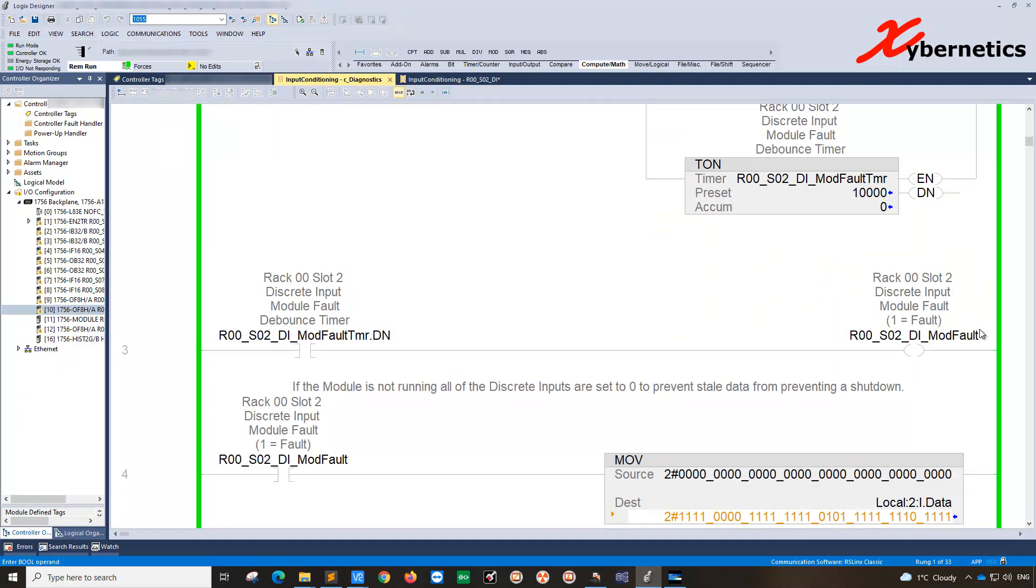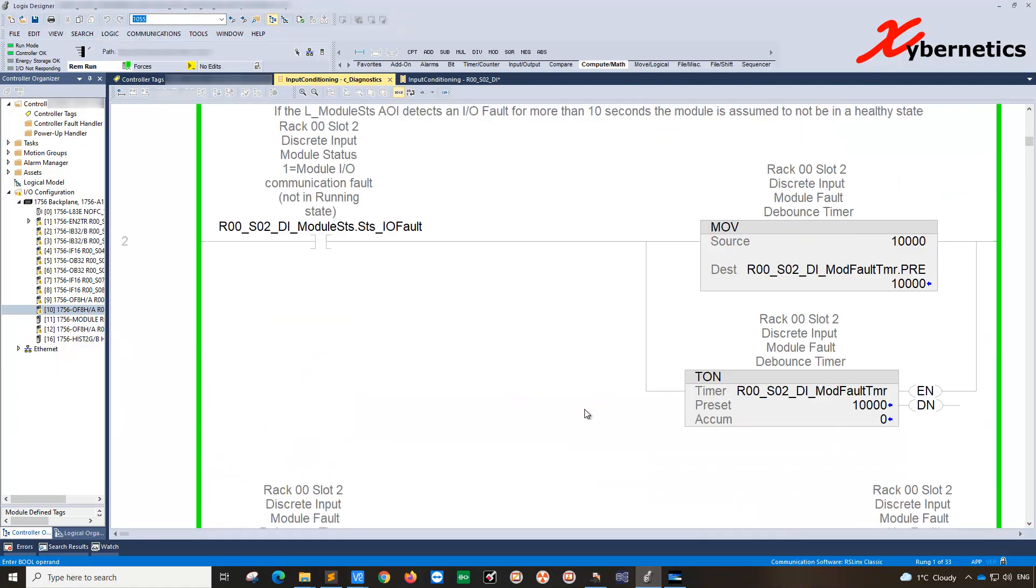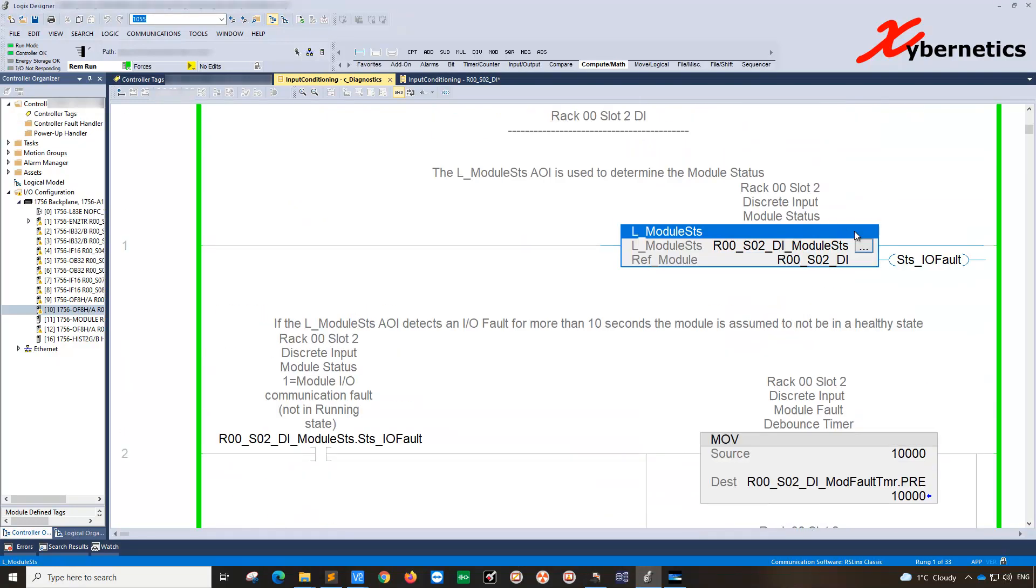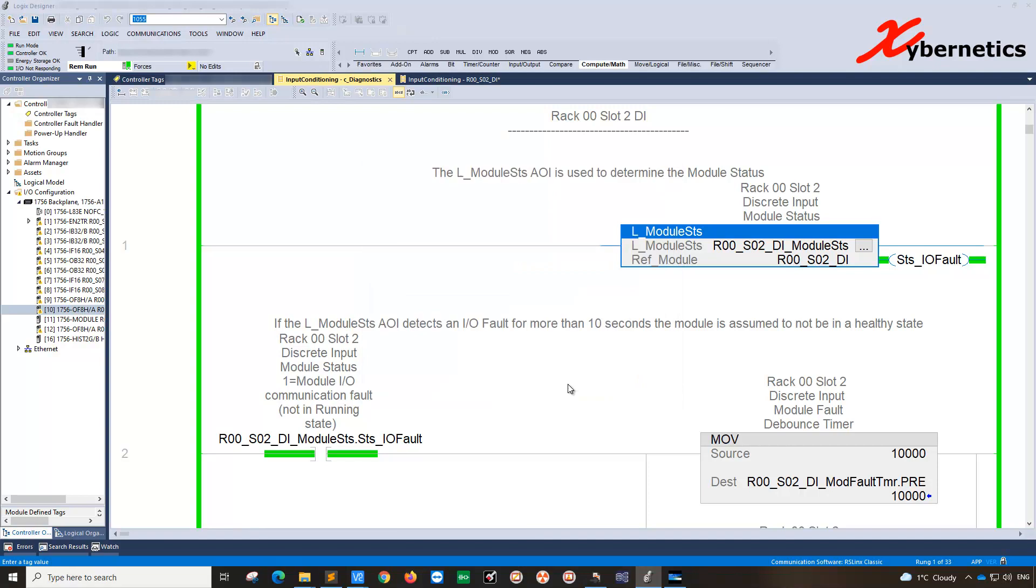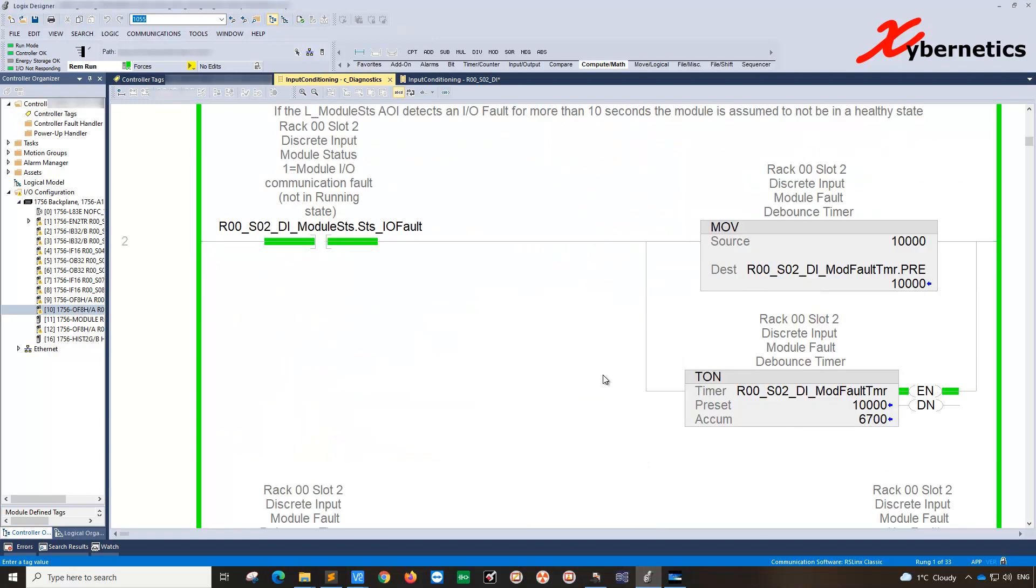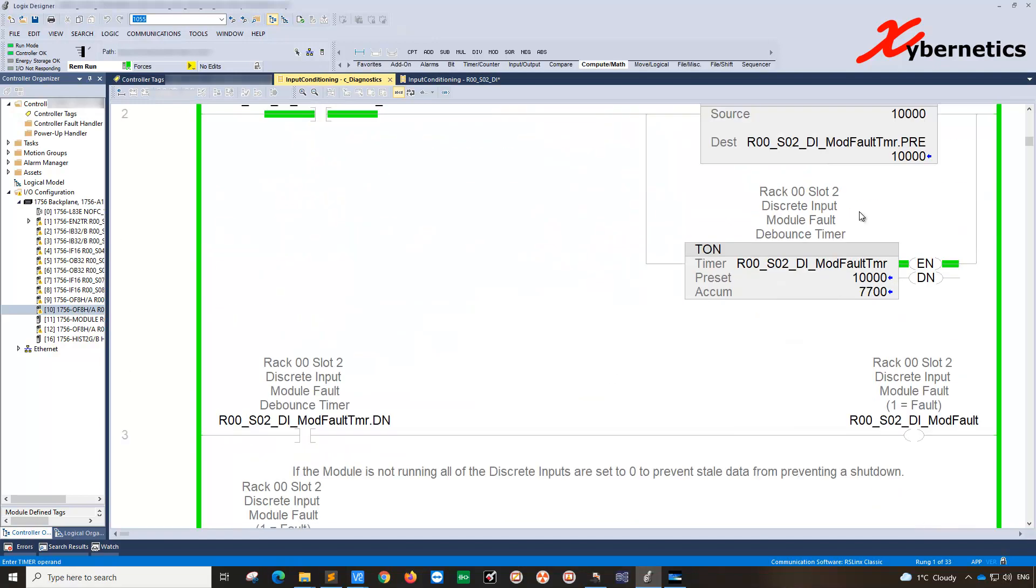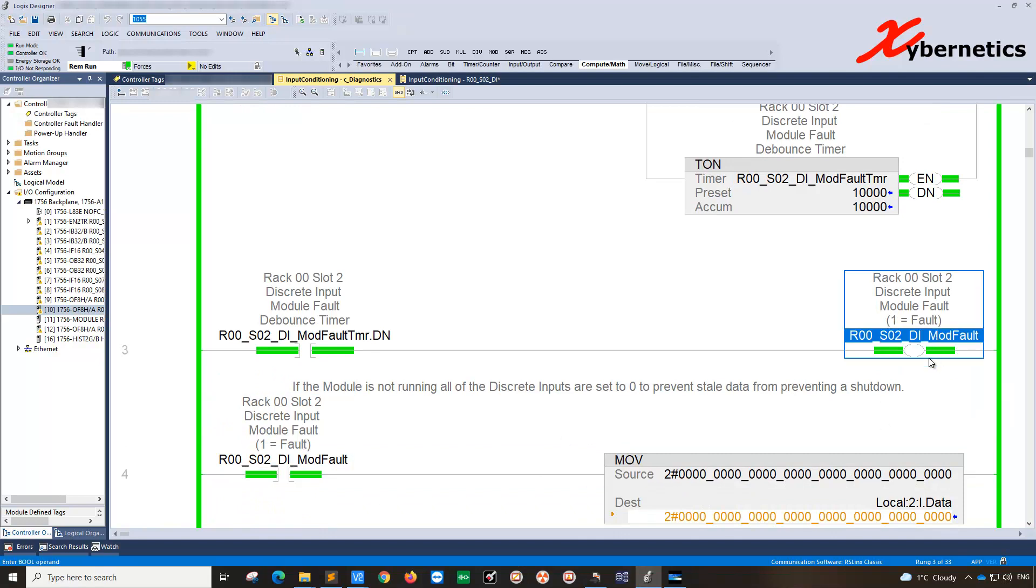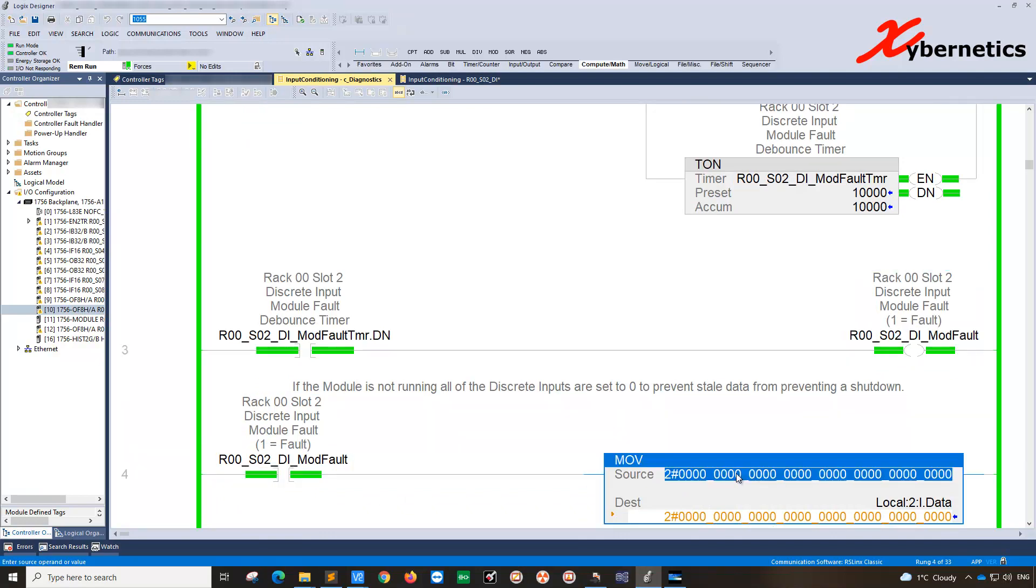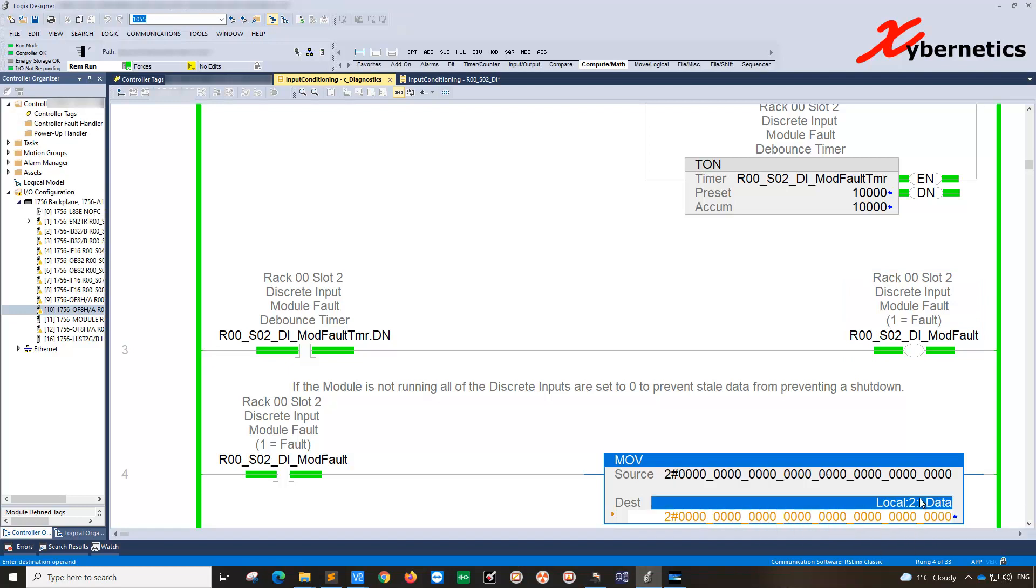If I were to remove from the simulation mode before you put into production and hit apply, you can see on a test bench the wires are not all hooked up correctly so your fault status will go to true. After 10 seconds has expired, you can see that the module fault is detected and a zero value is pushed to all the local channels.